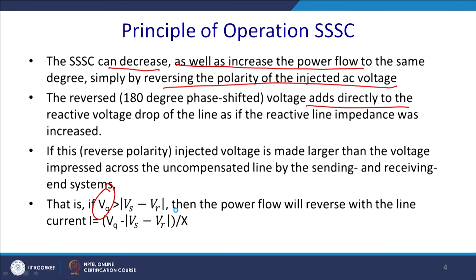If this reverse polarity injected voltage is made larger than the voltage impressed across the uncompensated line by the sending end and the receiving end voltage, that means if VQ is actually more than Vs minus Vr, then power will reverse, and the line current will also reverse, and I equal to VQ minus mod Vs minus Vr by X. So, current will flow in the negative direction. So, that is also possible.